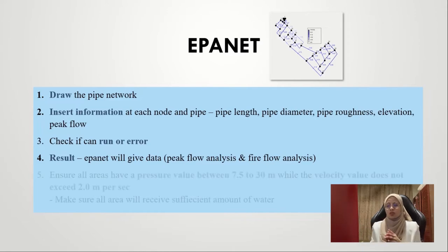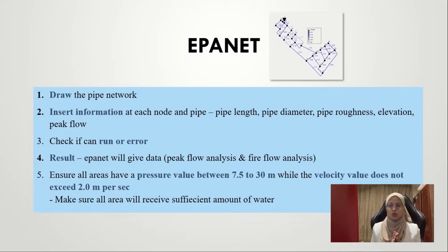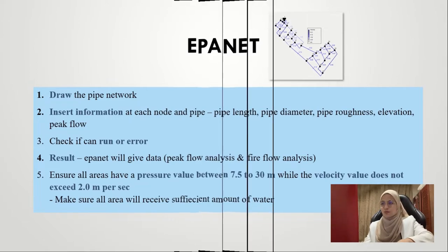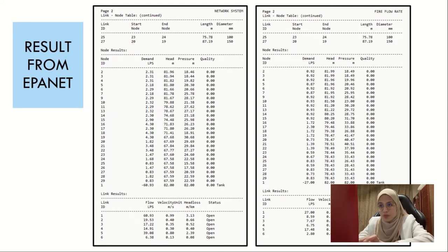From the results, we must check the data one by one to ensure that all areas have a pressure value between 7.5 to 30 meters and the velocity does not exceed 2 meters per second — to ensure all areas receive a sufficient amount of water. This is the result from ePanet. The left one is the result for peak flow analysis and the right one is for fire flow analysis. The parameters provided are head, pressure, velocity, flow, and head loss.